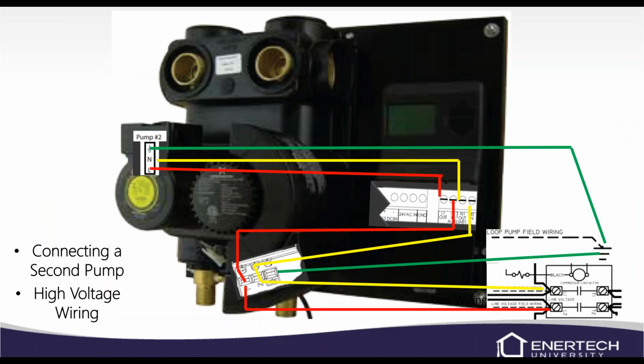If you've got a 2-pump flow center, it's a little bit confusing here. I know it's got a few lines going on, but basically what you're going to do is run from the contactor to your variable speed pump, because we need power to it all the time. You're going to piggyback on from the variable speed pump and take that high voltage to the controller. The controller will then decide, and you're going to run the power from the controller to the fixed speed pump. The controller will decide when it sends power to that second pump.